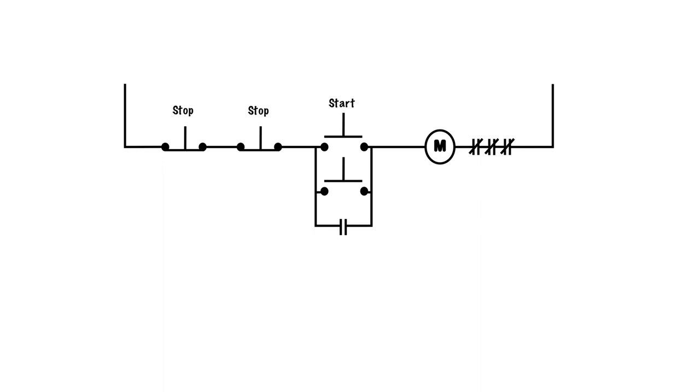This bounces back to its normally closed position. Power can get through right to these points here. It can't get across the start, it can't get across this start, and it can't get across the normally open contacts. M will stay de-energized up until the point you hit either this start button or this start button to energize M.